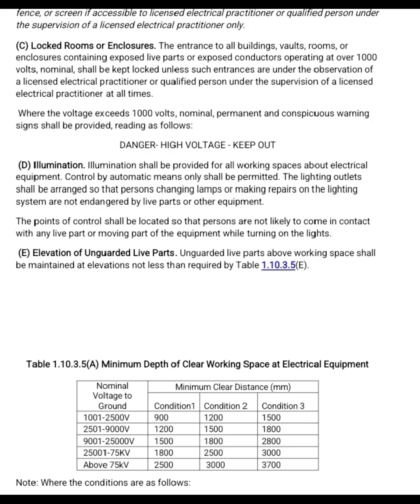Table 1.10.3.5a. Minimum depth of clear working space at electrical equipment. Nominal voltage to ground 1001 to 2500 volts: Condition 1, 900. Condition 2, 1200. Condition 3, 1500. 2501 to 9000 volts: Condition 1, 1200. Condition 2, 1500. Condition 3, 1800. 9001 to 25,000 volts: Condition 1, 1500. Condition 2, 1800. Condition 3, 2800. 25,001 to 75 kV: Condition 1, 1800. Condition 2, 2500. Condition 3, 3000. Above 75 kilovolts: Condition 1, 2500. Condition 2, 3000.